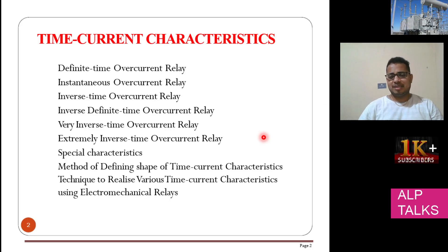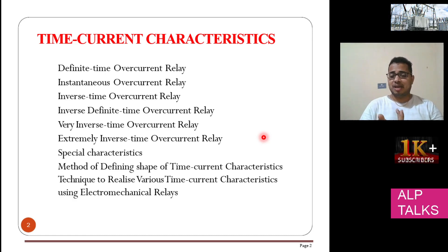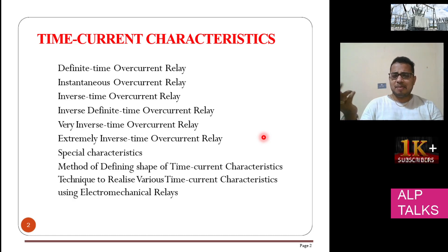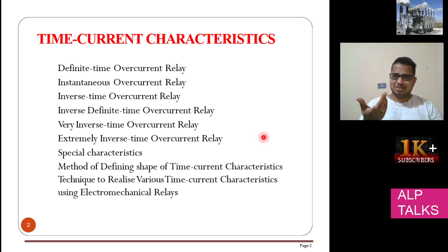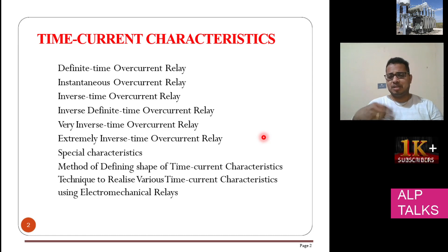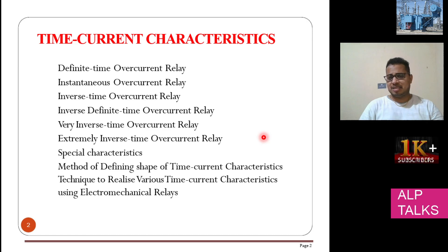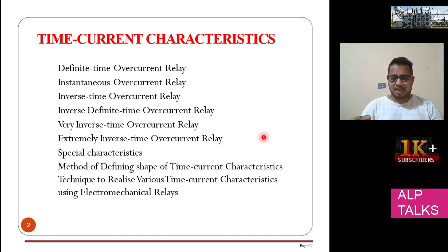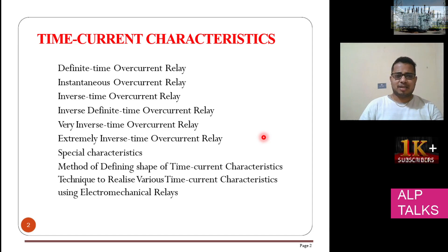There are certain things we have to consider in the overcurrent relay. For example, overcurrent means: say 100 amps is the normal current and 120 amps is flowing — then how long is that 120 amps flowing? For one or two seconds it may be okay, but if it persists for more than 10 seconds, then it is not okay. So there are time-related characteristics — time and current characteristics. One second is okay, two seconds is okay, but 10 or 20 seconds is not okay. So the operation is time-dependent — that is the time and current characteristic.